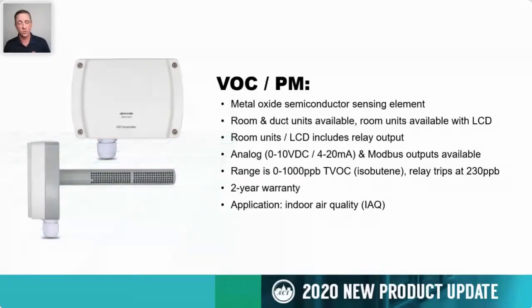Now, these are two different sensors. It's not both in one unit. So we have VOC and particulate matter sensors. These are available in room and duct configurations, both containing a metal oxide semiconductor sensing element. And if you get the room unit with LCD, it also includes a relay contact that trips at 230 parts per billion. These have analog or Modbus outputs, and the analogs are either 0 to 10 volt or 4 to 20 milliamp output. The range for the VOC device is 0 to 1,000 parts per billion of TVOC.